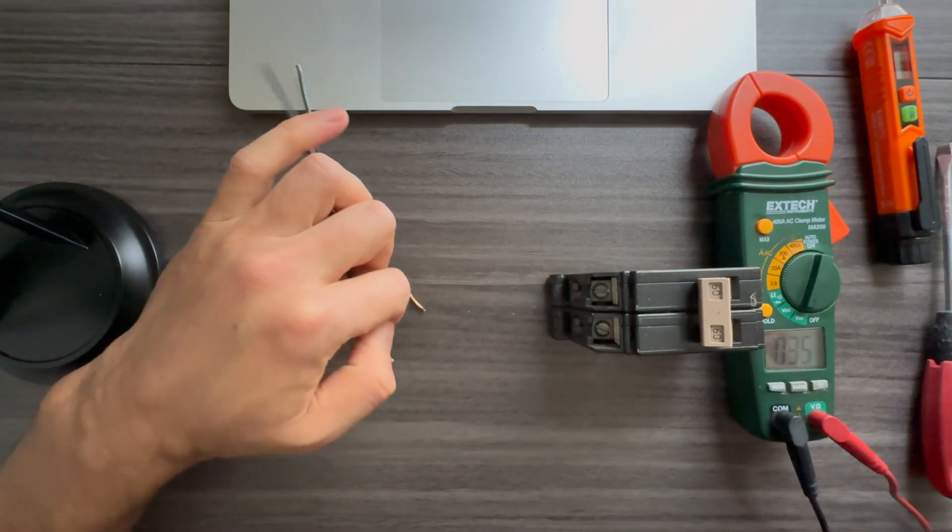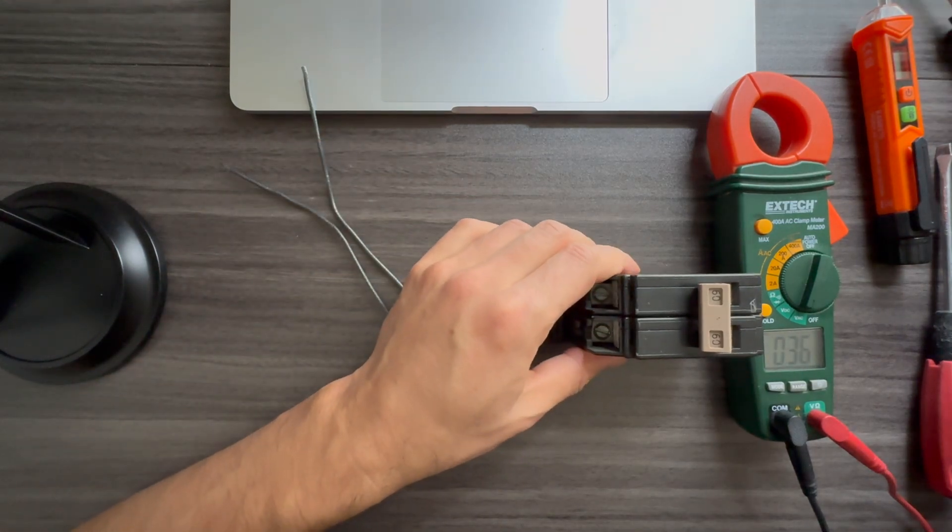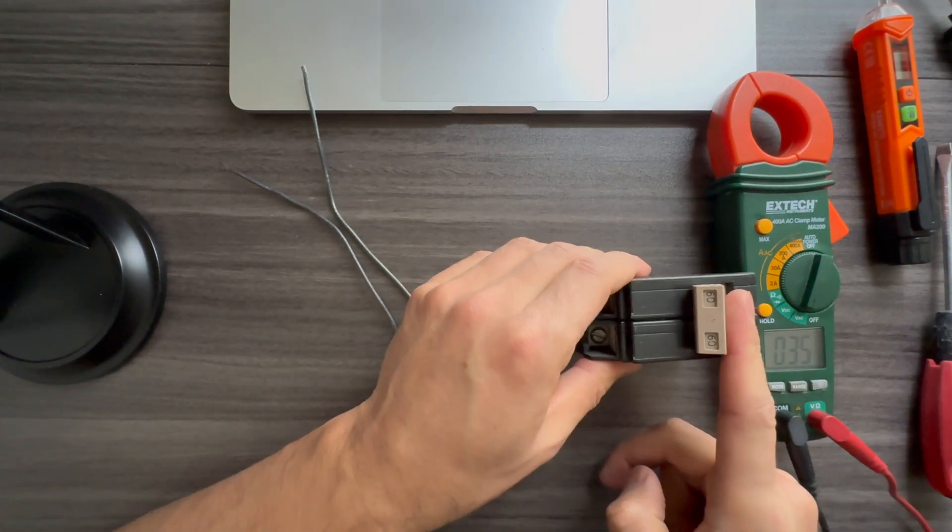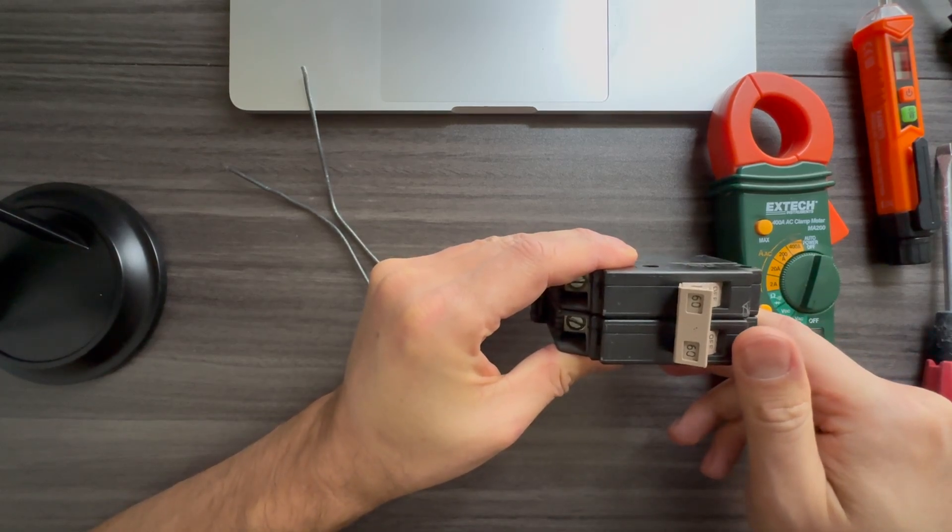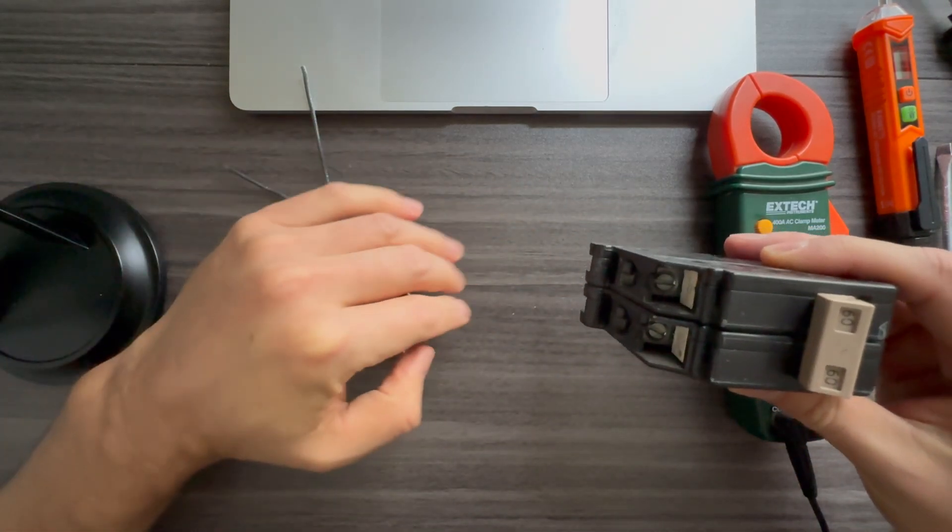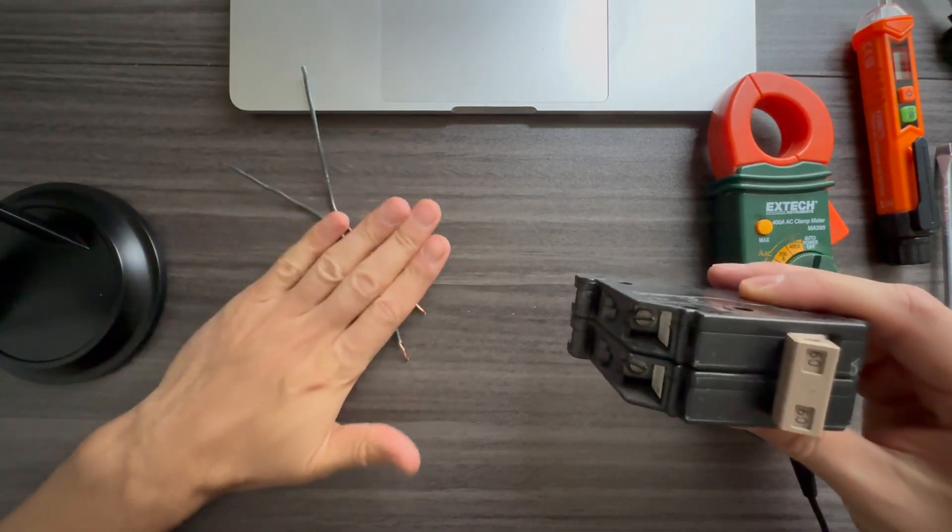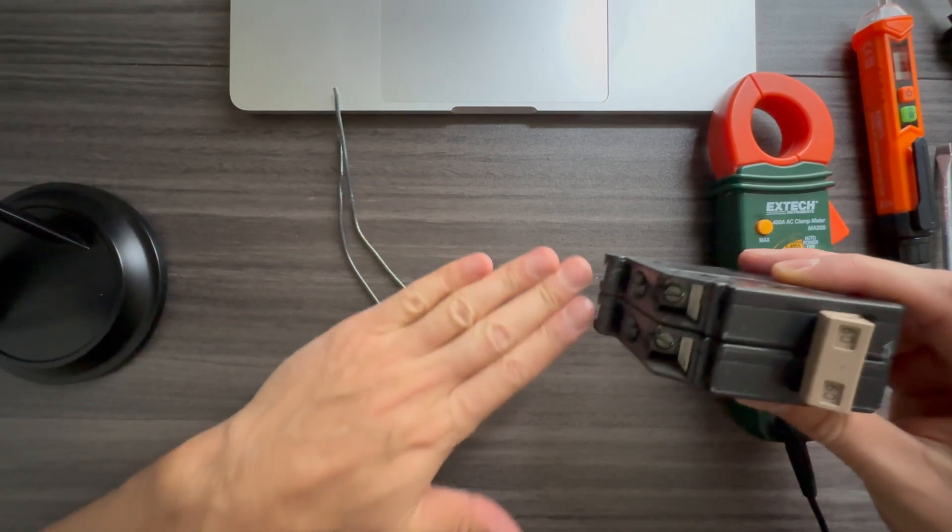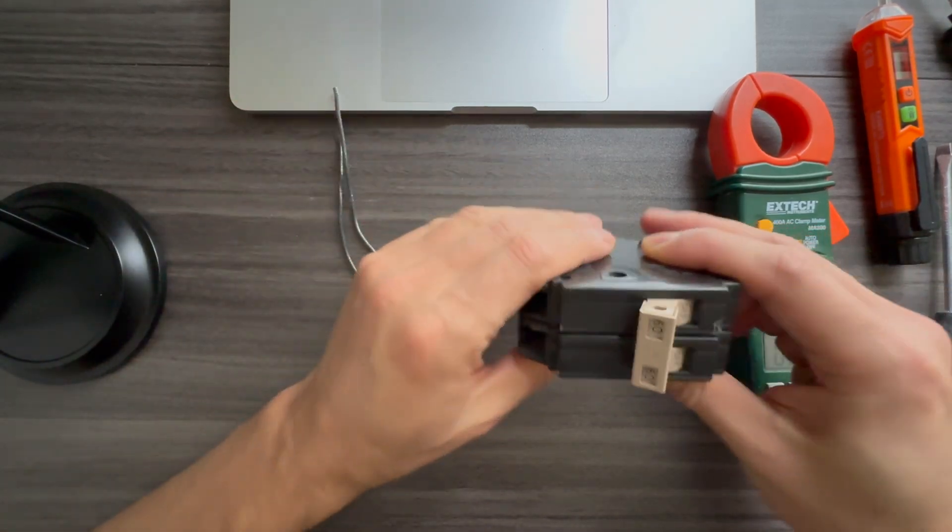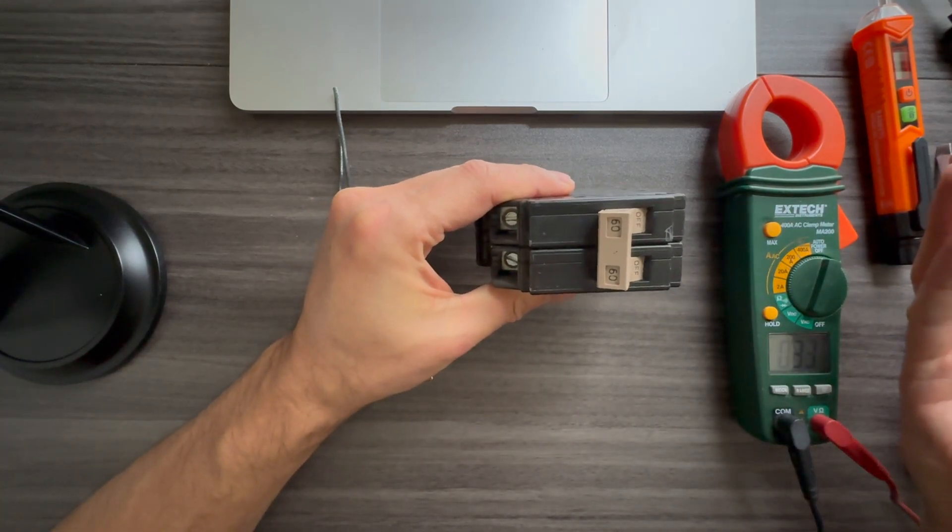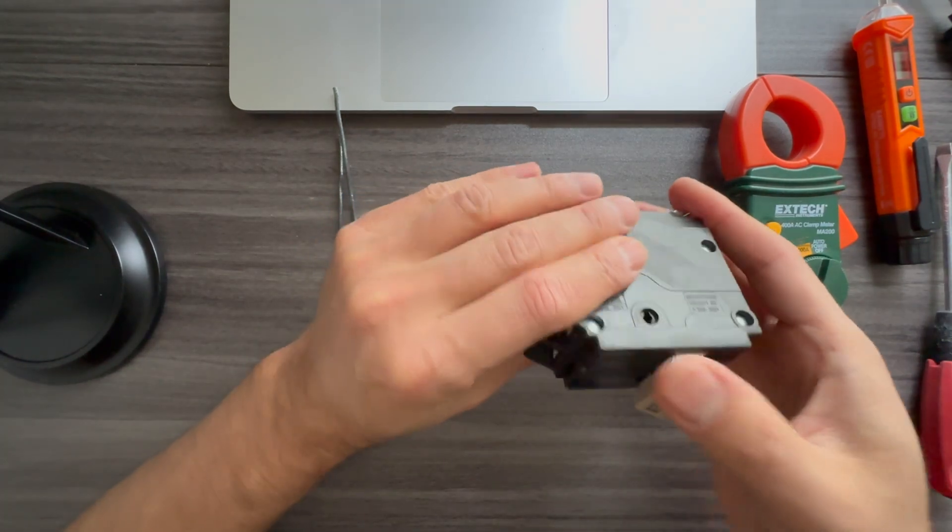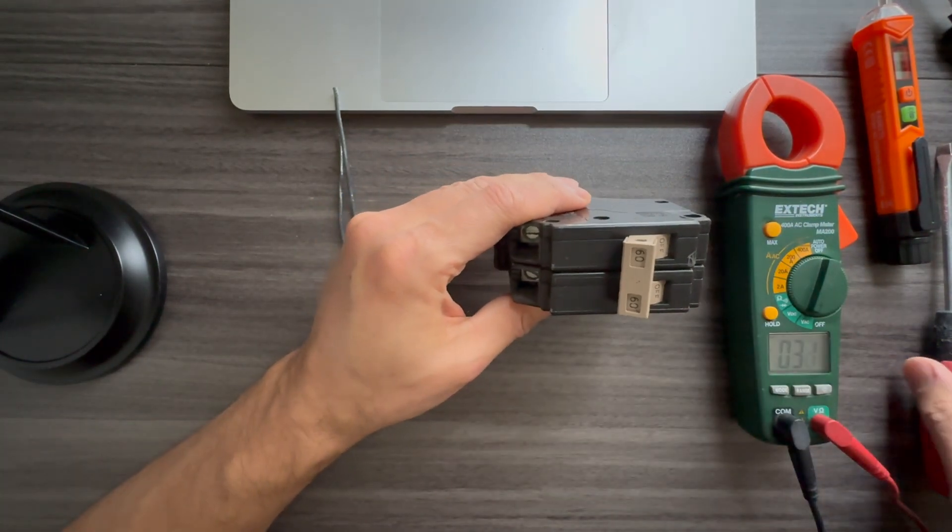So when you're trying to remove it, just be careful. So if it's a double pole, same situation. It's not turning on. When you try to turn it on, it goes back even after removing the wire, which means this is our load. Once we remove the load completely and we try to turn it on, it just doesn't turn on. That means this breaker is bad. It has to come off and it needs to be replaced.